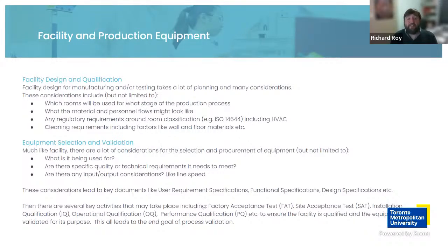And then going into equipment selection and validation, this is more specific to the production equipment and not necessarily the medical technology you're manufacturing. You're looking at what the equipment is being used for. Are there any specific quality or technical requirements that equipment needs to meet? And are there any input or output considerations, like, for example, line speed? If you're doing a high-throughput product, you of course want to know how many you're going to be able to make, and whether you're going to be able to meet market demand, as an example.